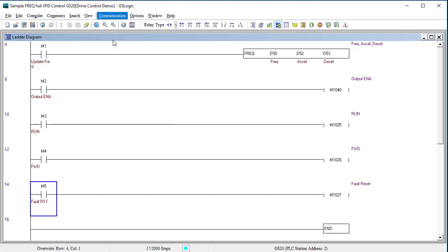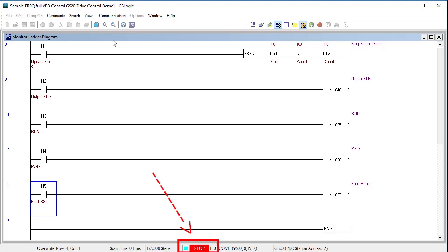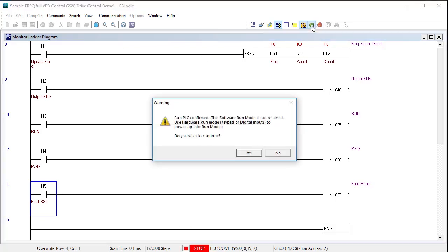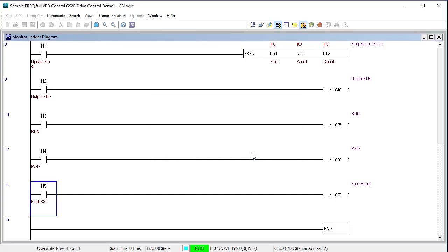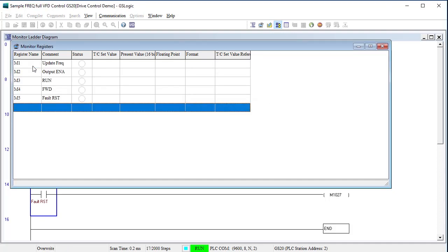Under the communications menu, we select online so we can monitor what the PLC is doing. Notice that this window is now labeled monitor ladder program. That serves as a reminder that we can't edit the code while monitoring the PLC. And we also now see that we are currently in stop mode. Click on this guy to switch to run mode. This reminds us this is temporary while we are using this GSLogic utility. How the drive acts on power up is determined by the drive's keypad menu or the digital inputs if you are using those to control the PLC.